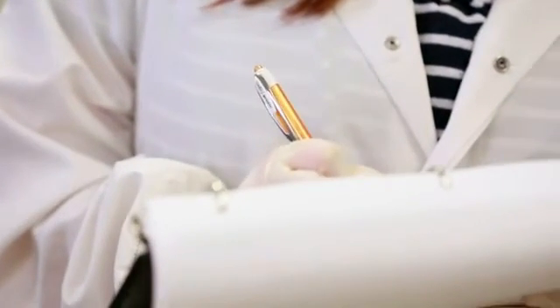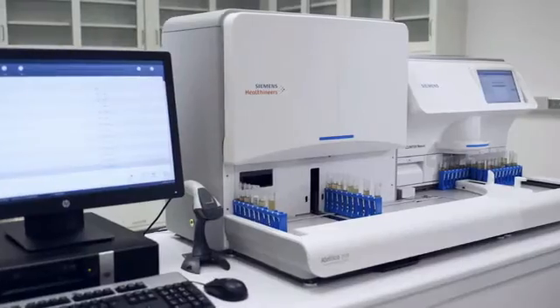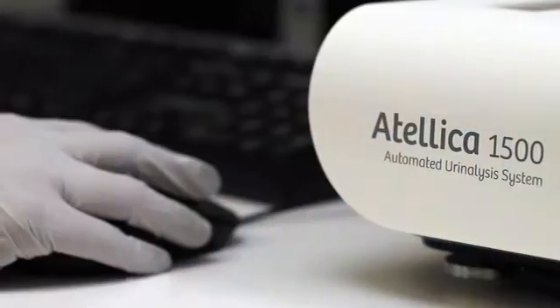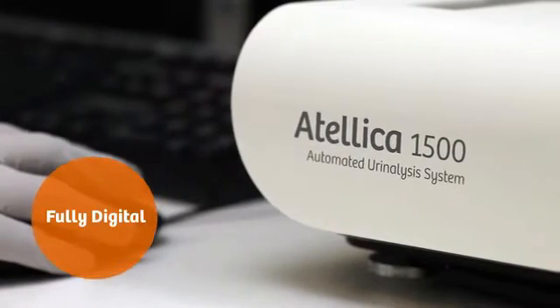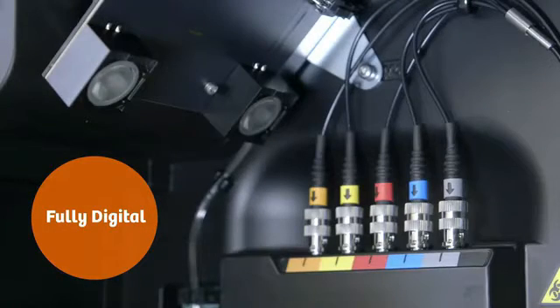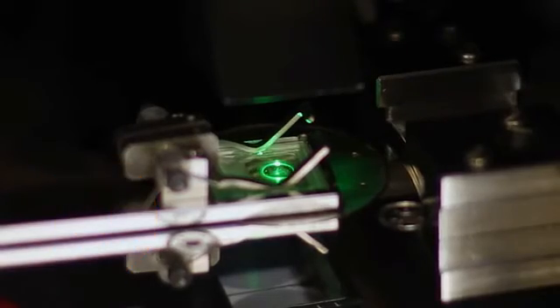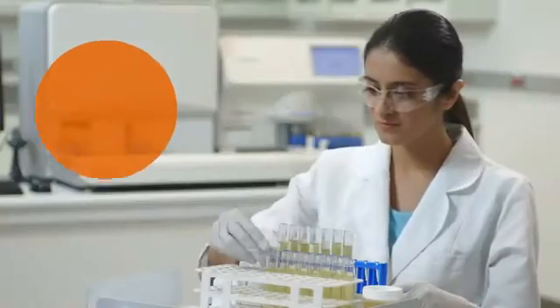The Atellica 1500 consists of a urine chemistry analyzer and a urine sediment analyzer, connected through a specially designed rack transport system. The Atellica 1500 automated urinalysis system is fully digital — it uses a digital camera to capture the urinalysis strips, and it uses advanced digital microscopy for sedimentation.